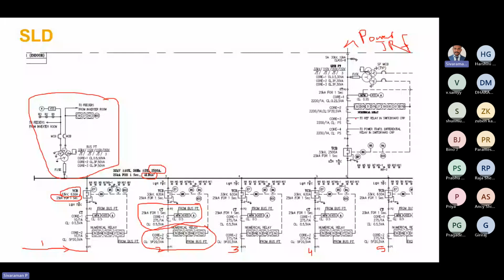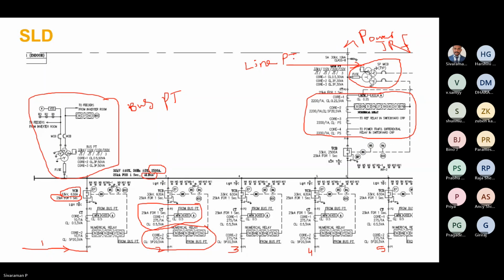Okay, so similarly on the outgoing side, again it will have a PT. In some projects a PT will be there additionally. So this is the CT for protection and metering purposes. Okay, so the PT connected to the common bus is called the bus PT. PT means potential transformer. Suppose the PT is connected to an individual line, whether it is the transformer line or the outgoing line to the solar plant, then this PT is called a line PT. Okay.